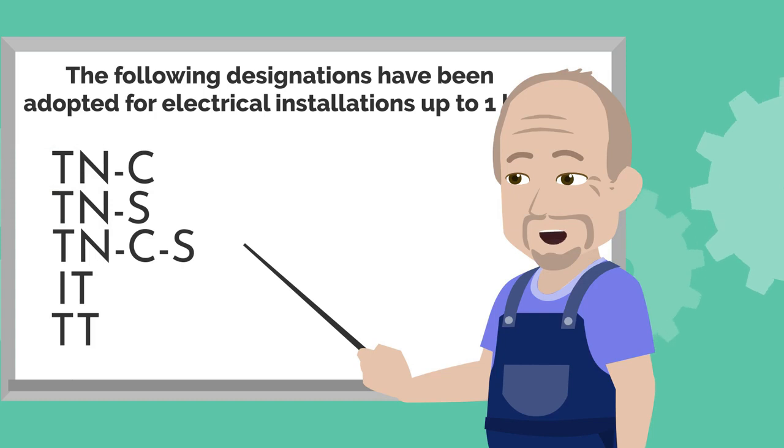T stands for the grounded neutral conductor. I means the insulated neutral conductor. The second letter indicates the grounding type of appliance's exposed parts. T means that exposed conducting elements are grounded. N indicates that conducting elements are connected to the grounded neutral conductor, while letters C and S describe the state of zero protective conductors. C means that they are connected. S stands for the separated conductors.